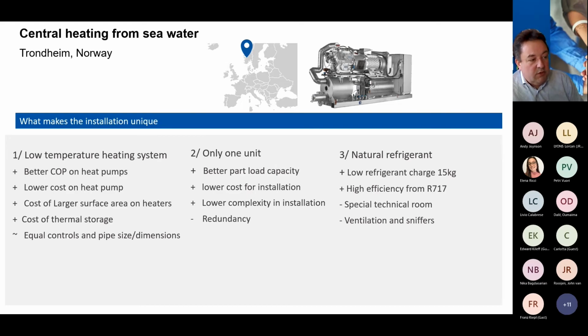You have to have some cost because a low temperature system will also demand a larger surface on your heating system, meaning heating surfaces on radiators and coils in ventilation systems. And then also add some cost to the building of thermal storage, meaning that you use the structure of the building to accumulate and equalize temperature changes, positive and negative. And one thing, a low temperature system actually has the same pipe dimensions because it's carrying the same number of kilowatt hours.